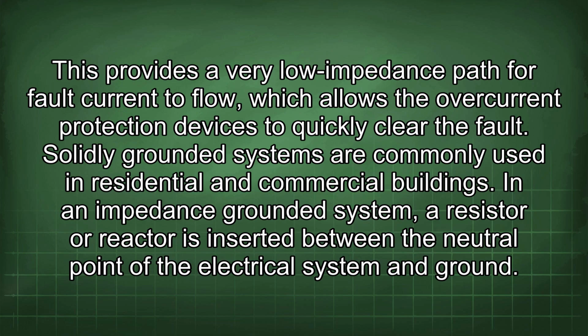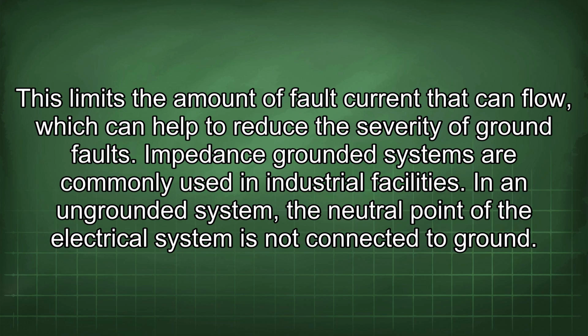In an impedance grounded system, a resistor or reactor is inserted between the neutral point of the electrical system and ground. This limits the amount of fault current that can flow, which can help to reduce the severity of ground faults. Impedance grounded systems are commonly used in industrial facilities.